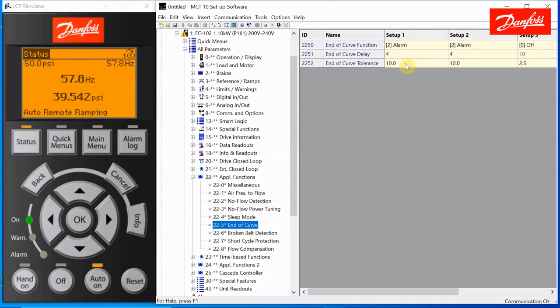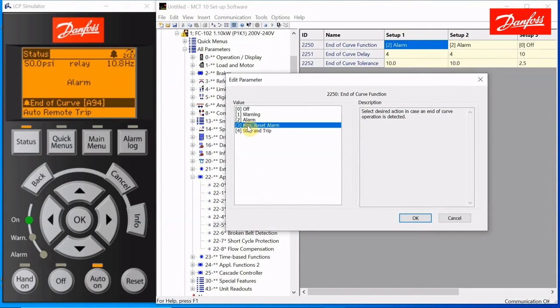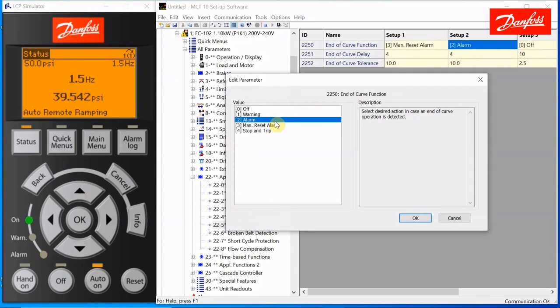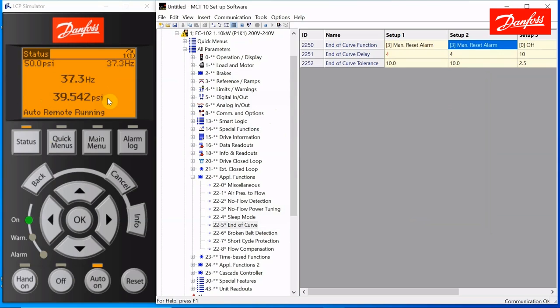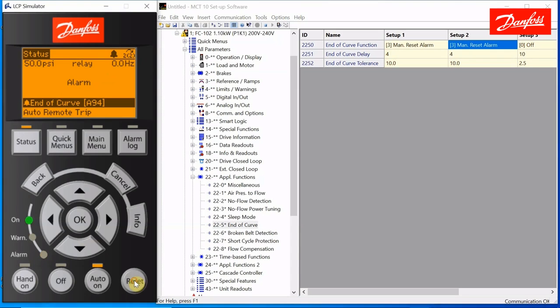So what do you do about that? Well, let's look at the next choice of end of curve function alarm, manual reset and alarm. If we choose that, your drive can automatically reset any other alarms, but this one in particular, it will not. So once that winds up to 60 hertz again, with the pressure below the trip threshold, dump that way down so it really ramps up more quickly, four seconds later, it shows the trip, triggers the relay, drops immediately to zero, and it will not reset automatically. It will require a manual reset, and once I do that, it takes off again.